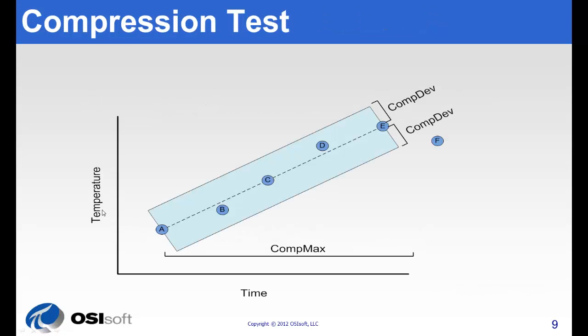The next test is the compression test. This is a more thorough test and defines which data is actually stored into the PI archives. What's special about this test compared to exception is that it has a slope. This is why we sometimes call it the swinging door algorithm. It's like a door viewed from above. It has a thickness and a length and it swings so that it can be at many different slopes. Again, like exception there are deviation settings and a maximum setting.